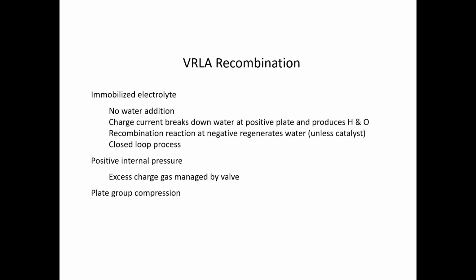There is positive internal pressure, as I mentioned before, usually about 3 to 5 psi. Gassing is managed by the valve, and compression is also an important part of the design of this battery. As I had on one of the previous slides, I showed the absorbed glass mat, not only keeping the cells from shorting out as a separator, but it also holds the electrolyte. It's important to have physical contact between that glass mat and those plates, so the electrochemical reaction has a path. And that's a lot of what those testers or meters are looking at.